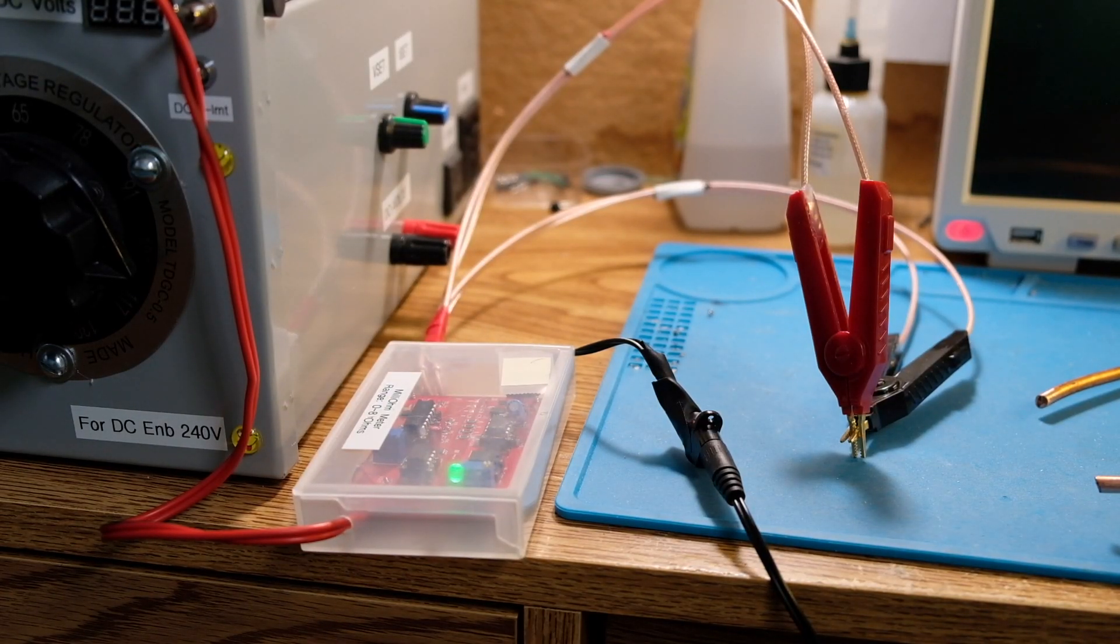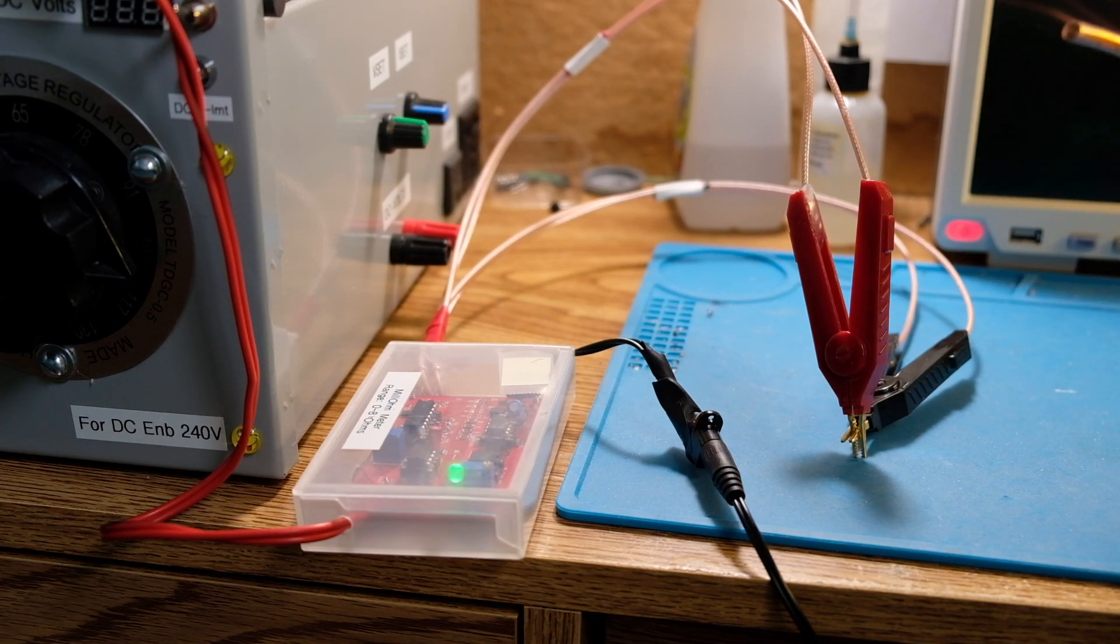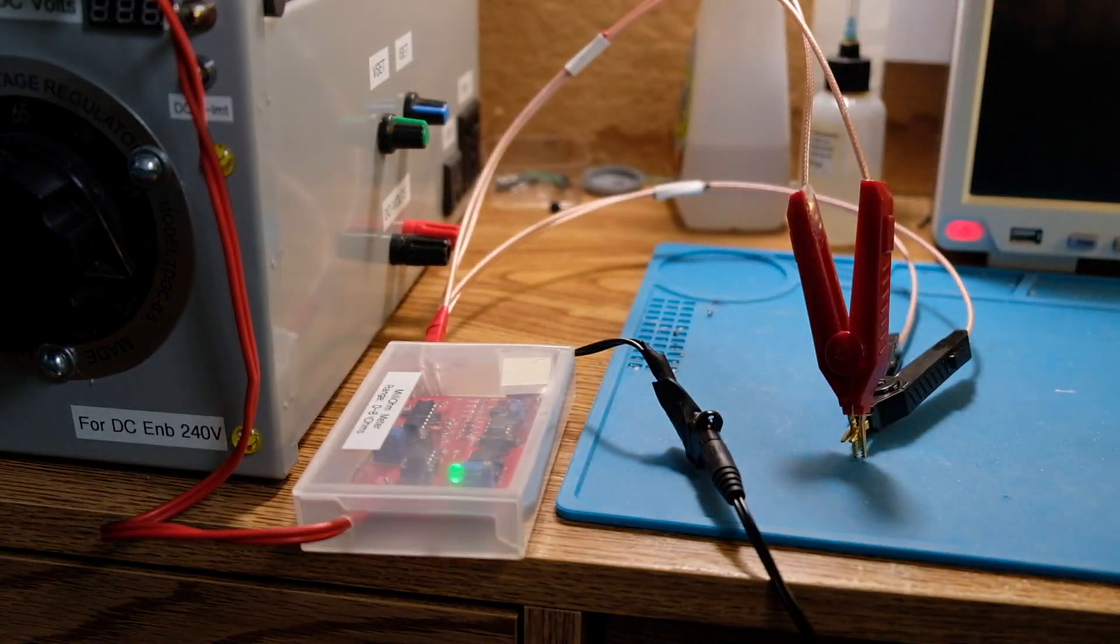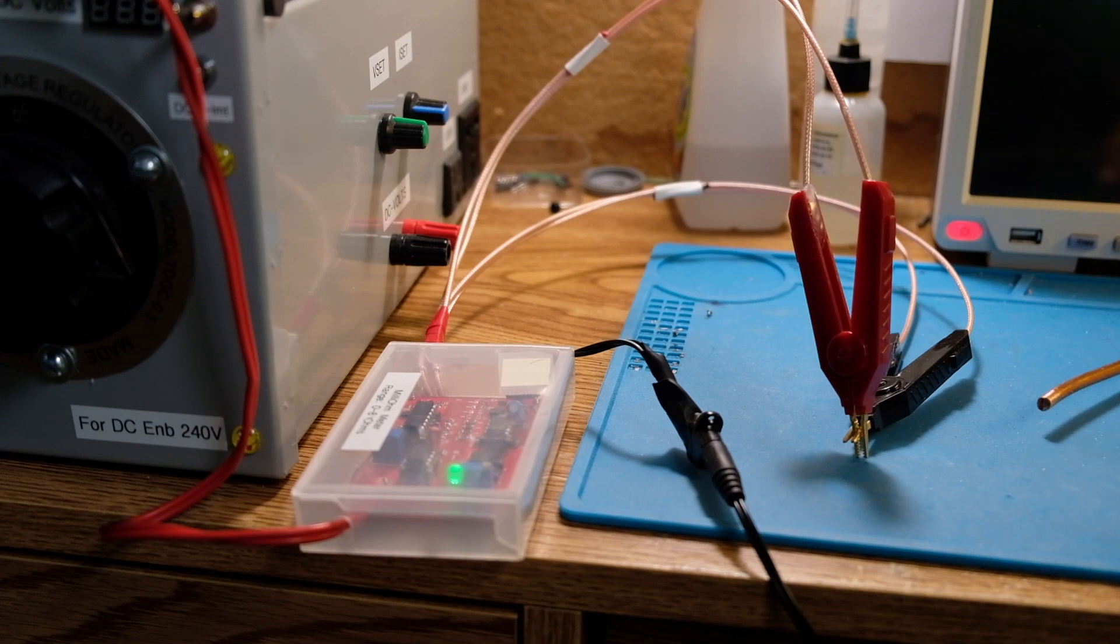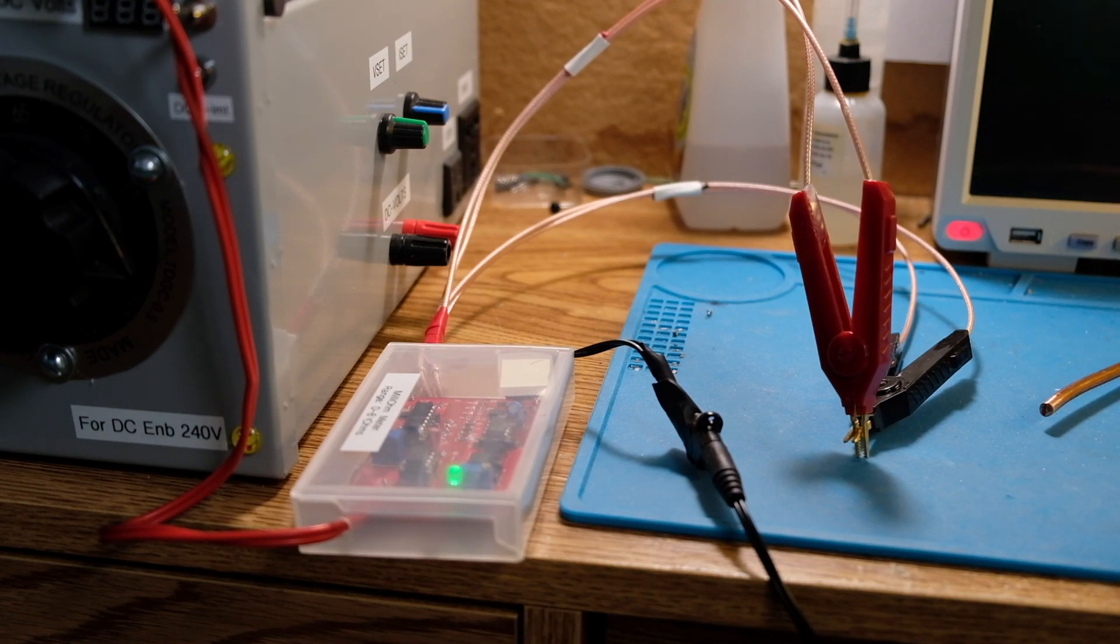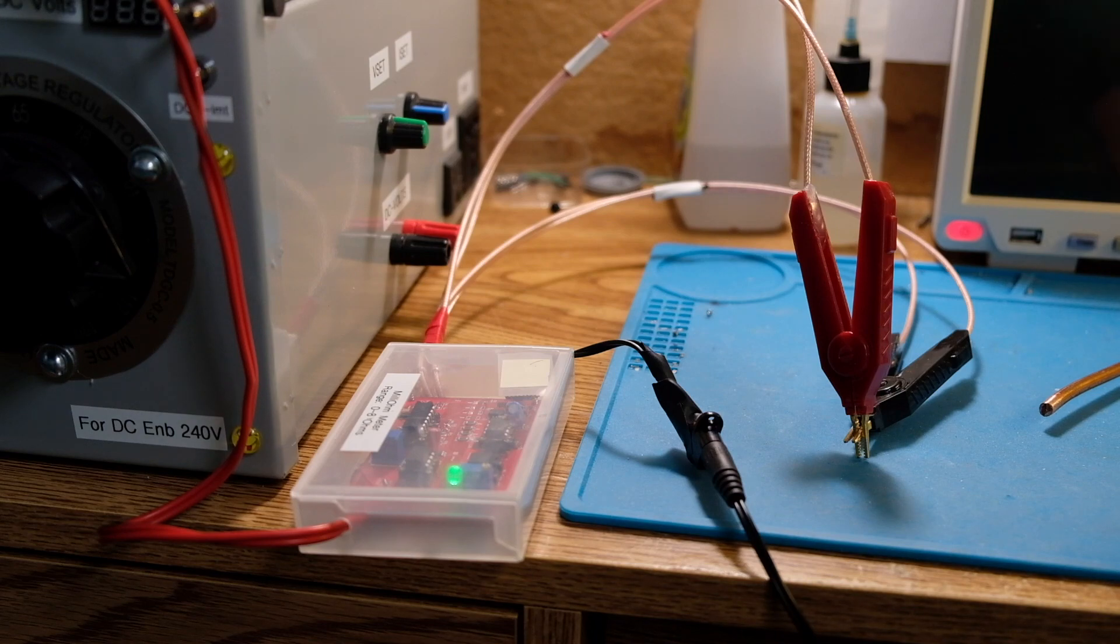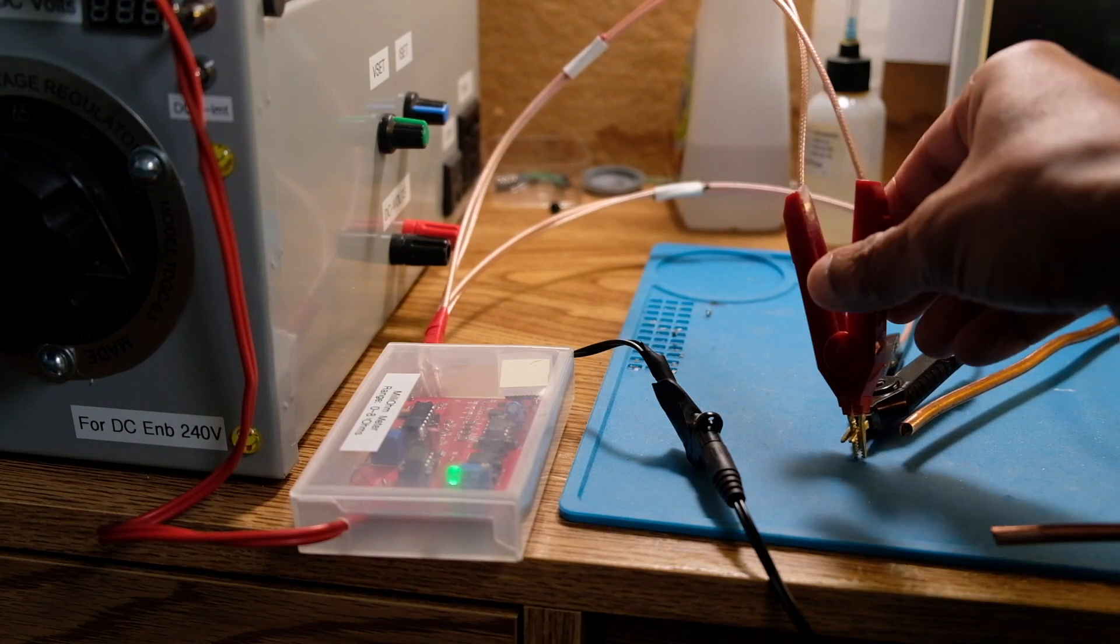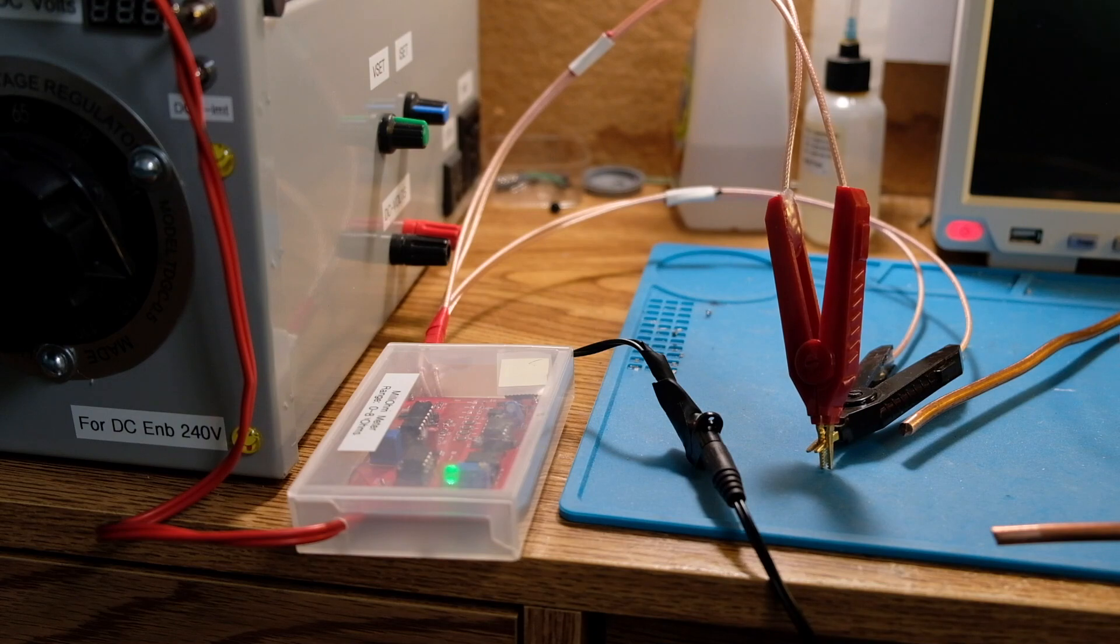Here's the setup to do a low resistance measurement of a very thick copper wire. As you can see, this wire here is very solid, barely bendable. It's number 4, the diameter is 0.2 inches AWG4. Length is 1.6 meters or 1.58 meters to be exact, and right now I've shorted the Kelvin clamps as best as I could.